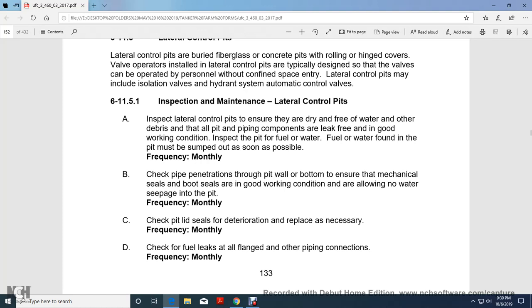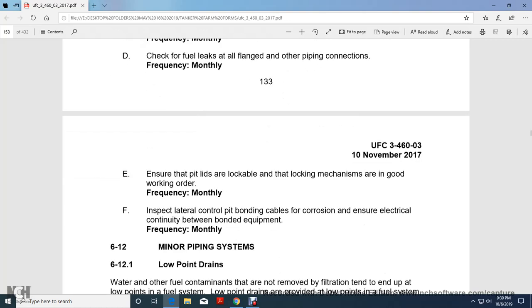Inspect lateral control pits to ensure that they are dry and free of water and other debris, and that all piping components are leak free and in good working condition. Inspect the pit for fuel and water. Fuel and water found in the pit must be sumped out as soon as possible, monthly. Check the pipe penetrations through the pit wall at the bottom to ensure the mechanical boot seals are in good working condition and allowing no water seepage into the pit, monthly. Check the pit lid seals for deterioration, and replace as necessary. Check monthly for fuel leaks at flange and other piping connections.